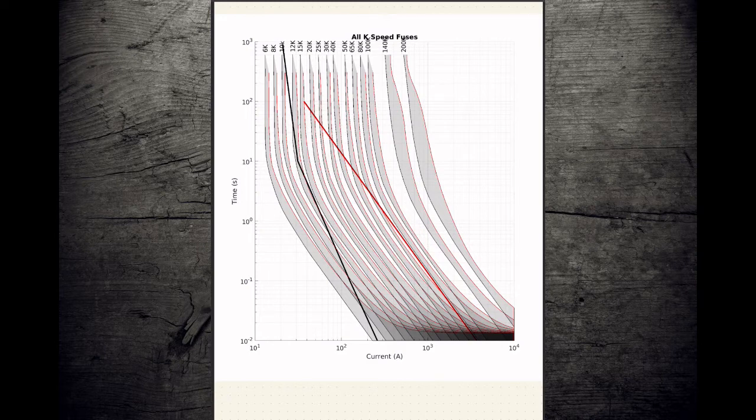So your damage curve should be perfectly straight. If you find that it's looking wavy, again, check your points. Your inrush curve should have the lower 4 points perfectly in line. And then the last point, you're going to find has a little bit of an elbow to it. But these lower 4 points should be aligned perfectly.